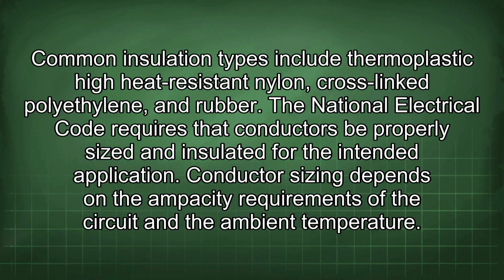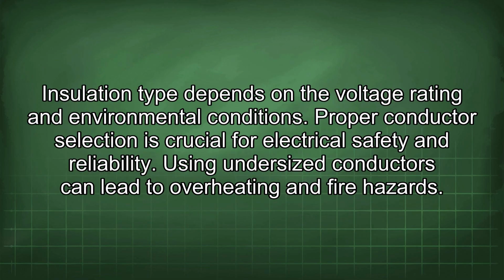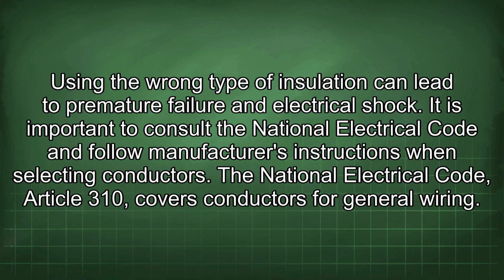Conductor sizing depends on the ampacity requirements of the circuit and the ambient temperature. Insulation type depends on the voltage rating and environmental conditions. Proper conductor selection is crucial for electrical safety and reliability. Using undersized conductors can lead to overheating and fire hazards. Using the wrong type of insulation can lead to premature failure and electrical shock. It is important to consult the National Electrical Code and follow manufacturer's instructions when selecting conductors.